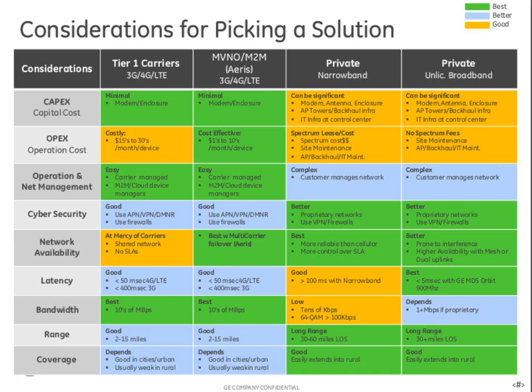Latency is usually manageable for most applications. For 3G cellular networks, it's typically 400 to 500 milliseconds for M2M, sometimes down to 200 or 300. That's fine for most applications, but once you're talking about protection, like 61850 Goose, you need less than 100 milliseconds. So you'd need 4G LTE, which we've tested as low as 35 milliseconds one way on the Verizon network, or private unlicensed broadband.